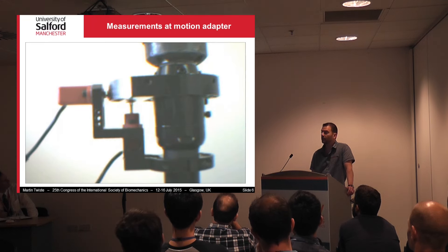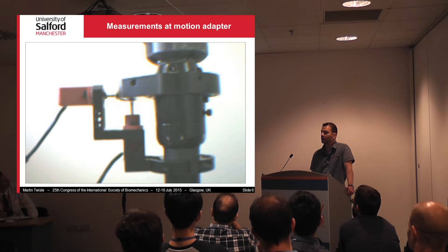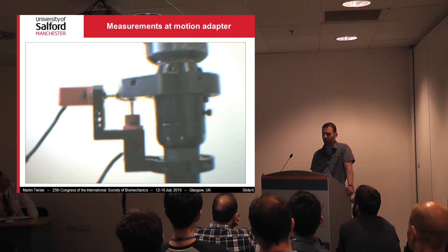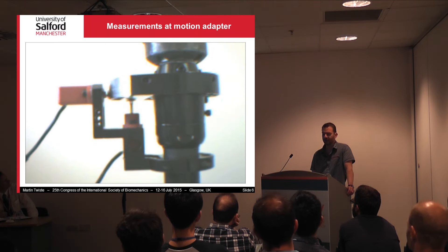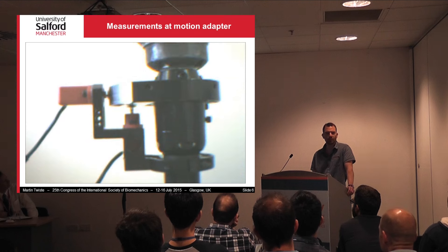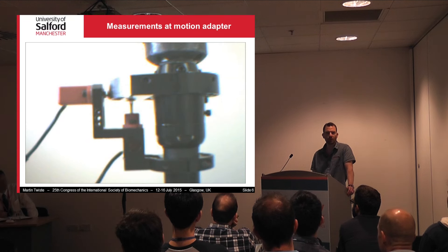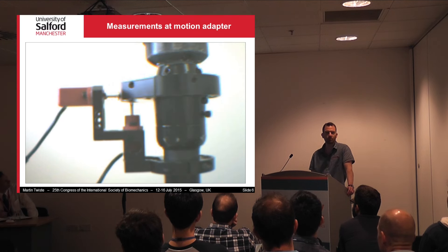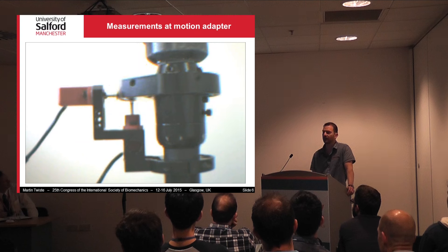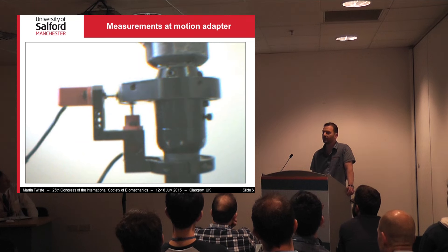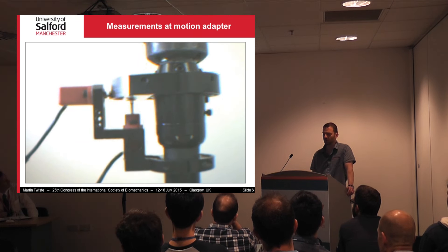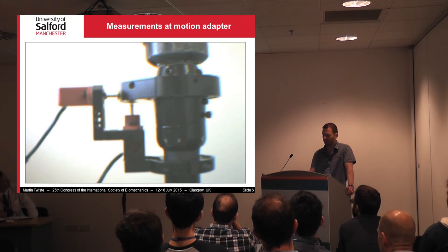Here you can see the motion adapter in action — you can see how transverse rotation can take place without affecting the plunger for longitudinal translation, and vice versa. So we essentially decoupled the two motions and could measure them independently.